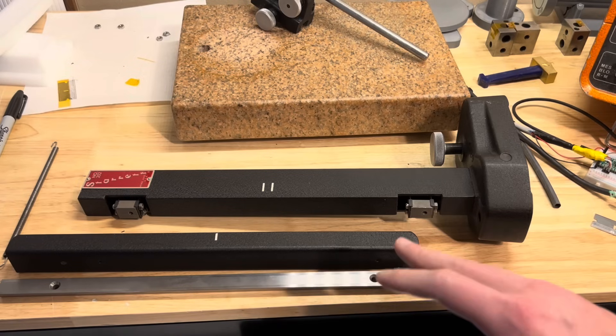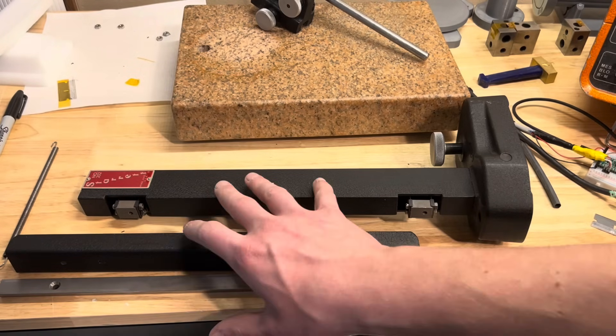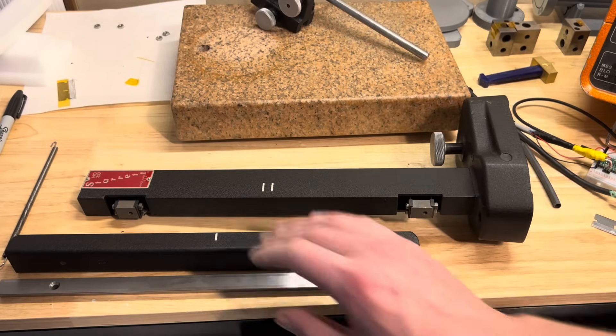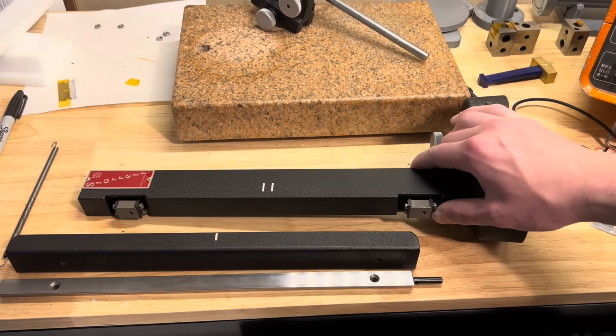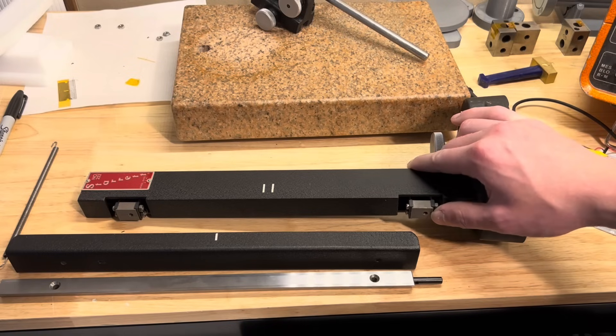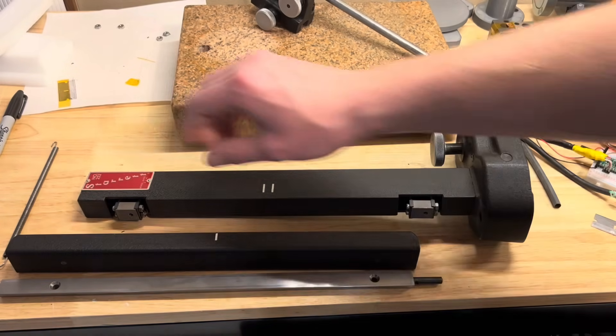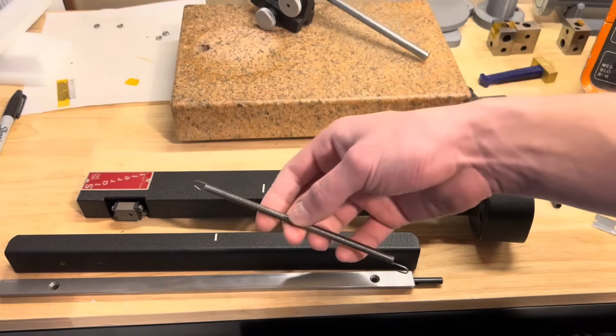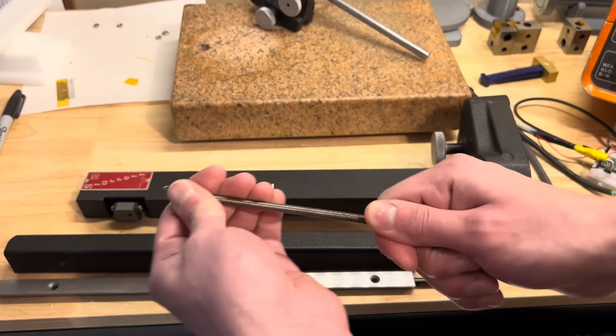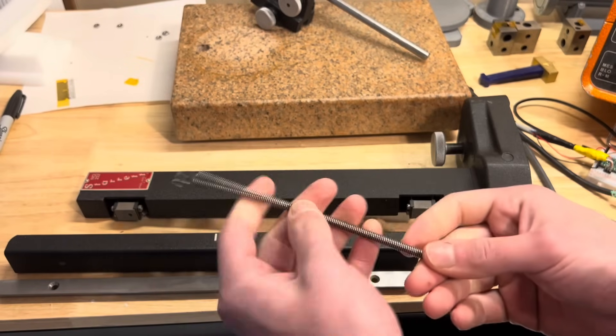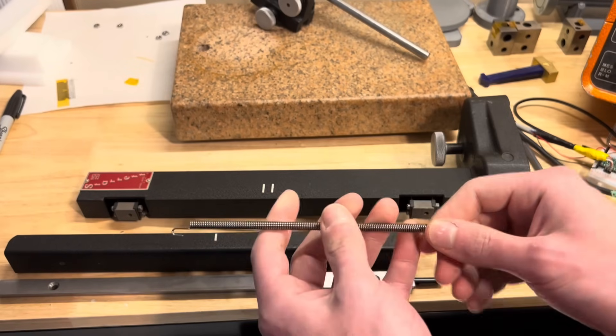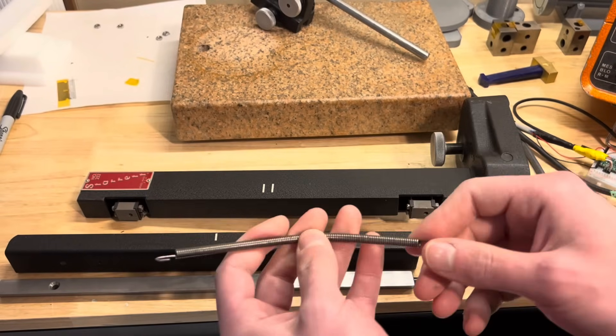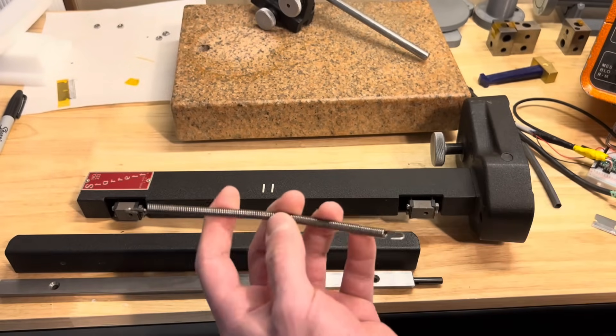Now, where I think the problems are coming from is the method that is used to sort of preload this whole stage against the rocker bar down here. You could just use the inherent restoring force from the stiffness of the flexure stages, but these aren't super stiff. You want a little bit more, I guess. And this is what I found inside that they used very surprisingly stiff spring here. And I think this is where our noise excitation is coming from.